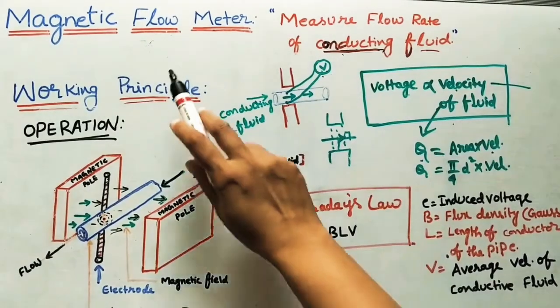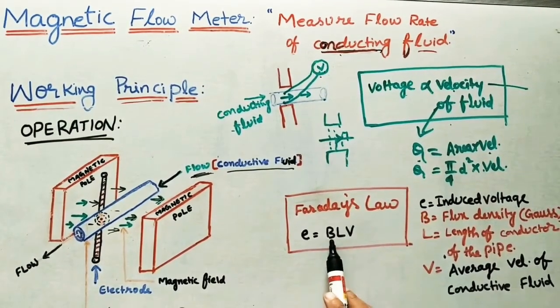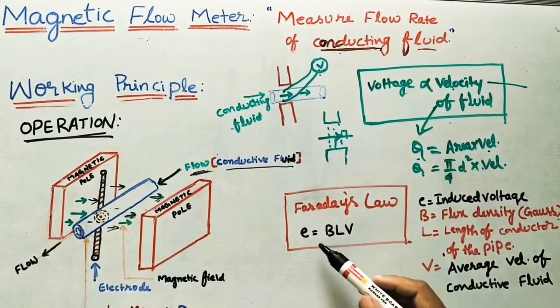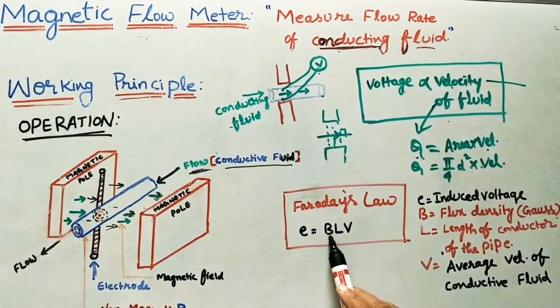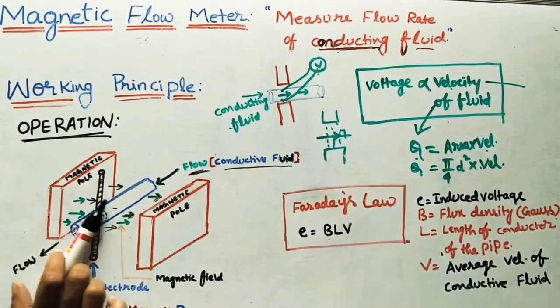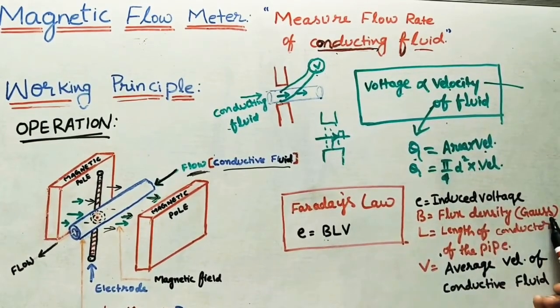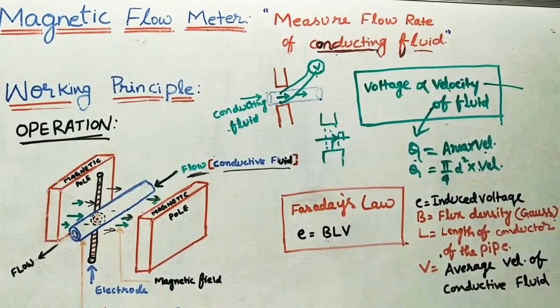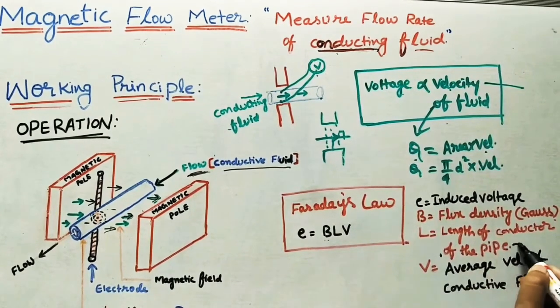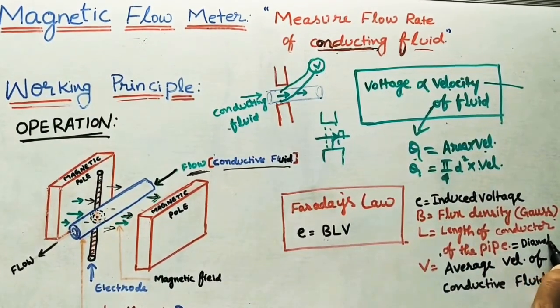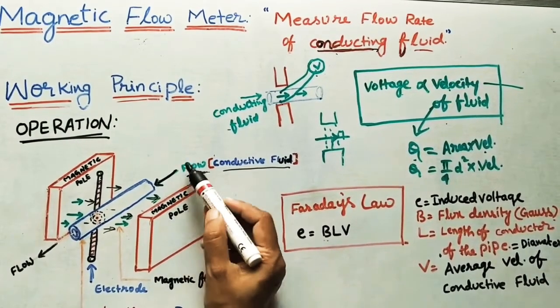This magnetic flow meter follows Faraday's law. According to this law, the induced voltage E equals B × L × V. Here, E is the induced voltage, B is the magnetic flux density — the density of the magnetic field, with units in Gauss. L is the conducting length of the pipe — that is, the diameter of the pipe from one side to the other. V is the average velocity of the flowing fluid.